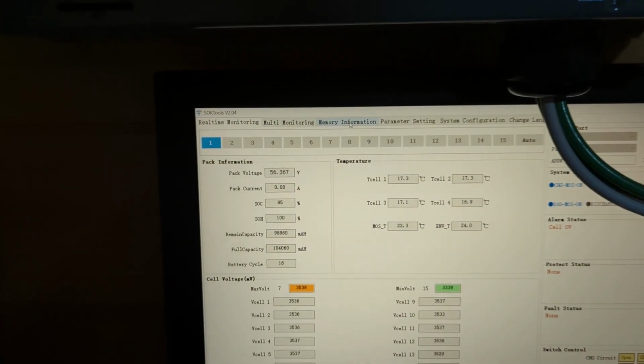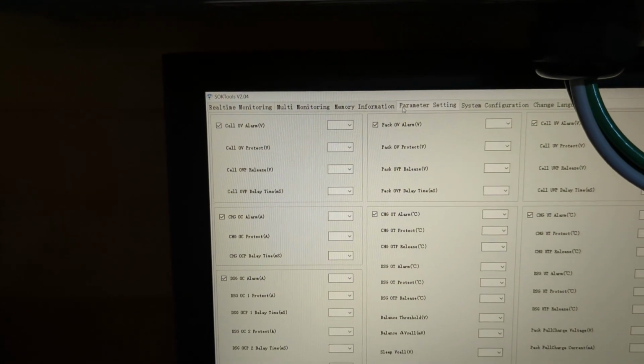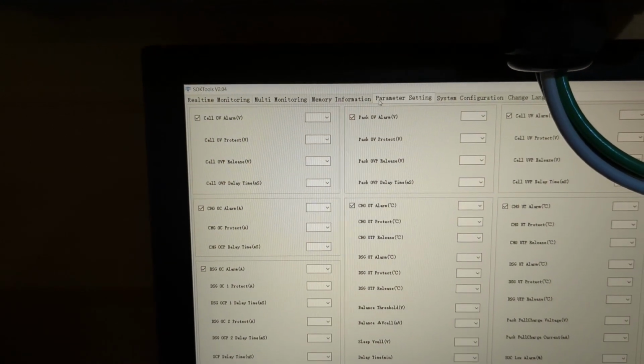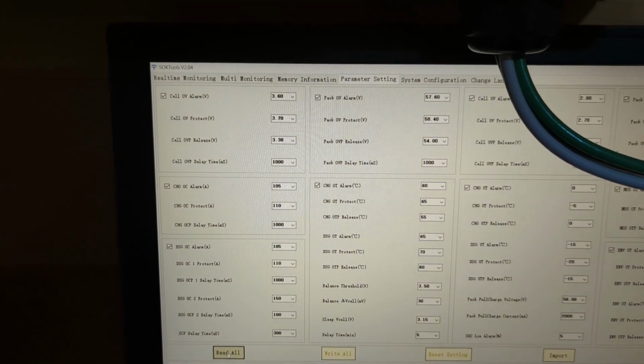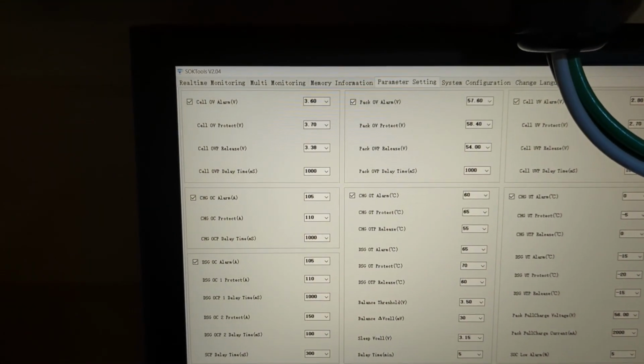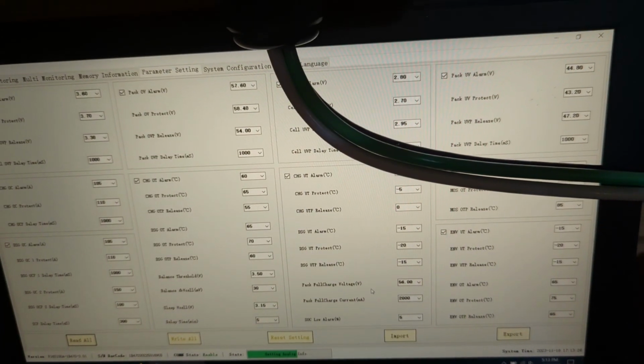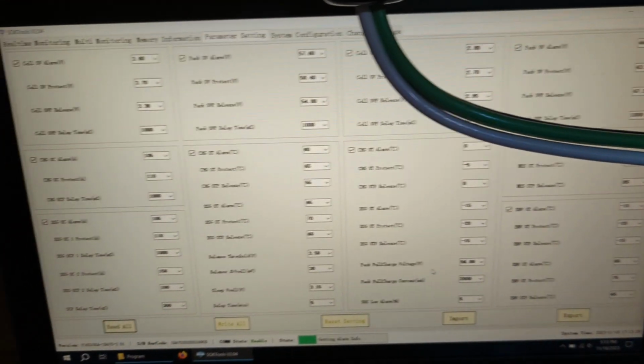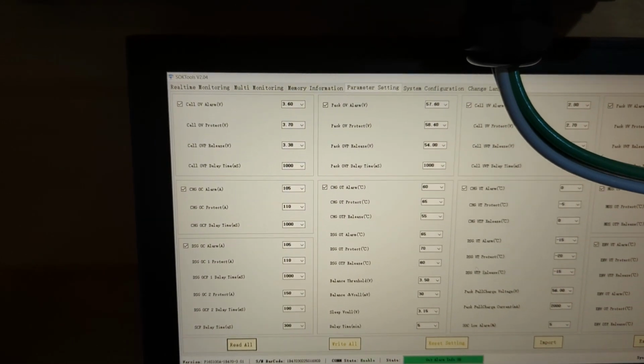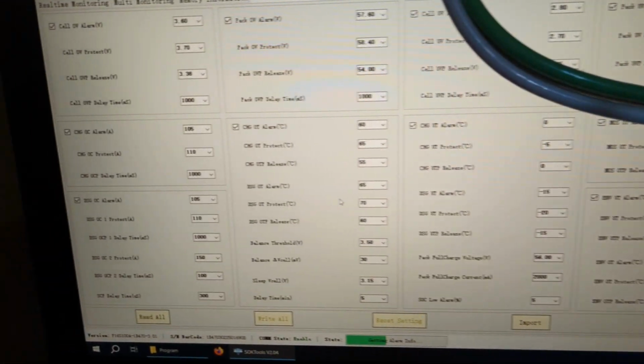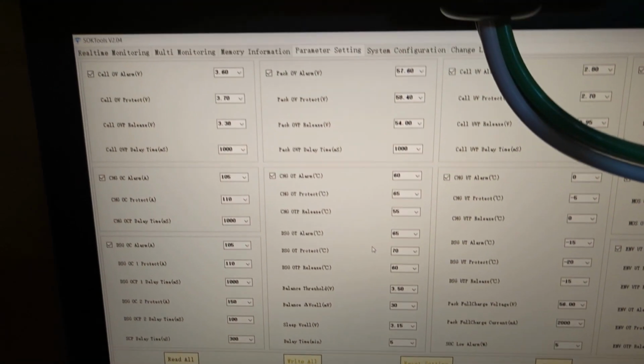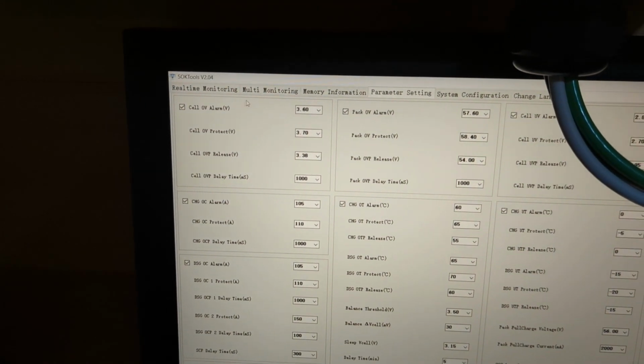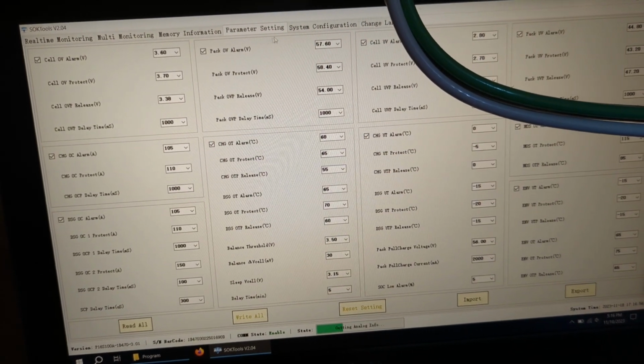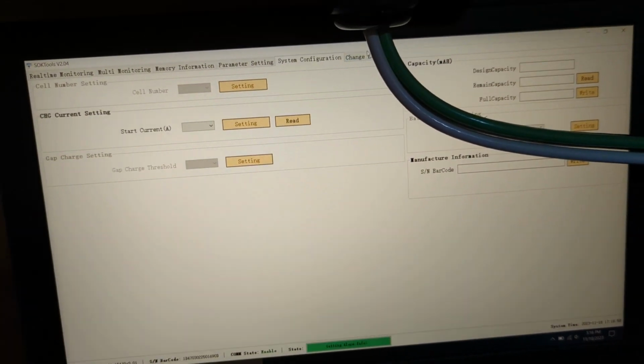If you click over to parameter settings, this is the tab where you can see what the BMS is programmed to. So let's check read all, and we can see the allowed discharge current for the BMS. I didn't show this page the first time around when I demonstrated the BMS problem. It does appear to be programmed correctly, but it just won't allow it. I don't have the ability to modify any of these settings because it is firmware locked.